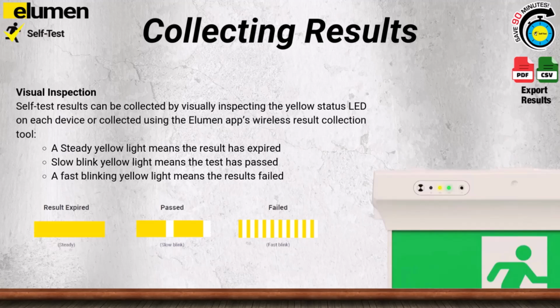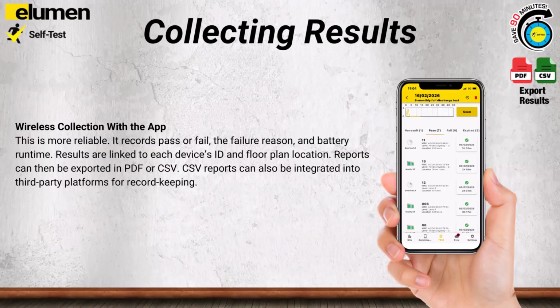Results can be collected 2 ways. Visual inspection. Self-test results can be collected by visually inspecting the yellow status LED on each device, or collected using the Elumen app's wireless result collection tool. A steady yellow light means the result has expired. Slow blink yellow light means test has passed. Fast blinking yellow light means the results failed.